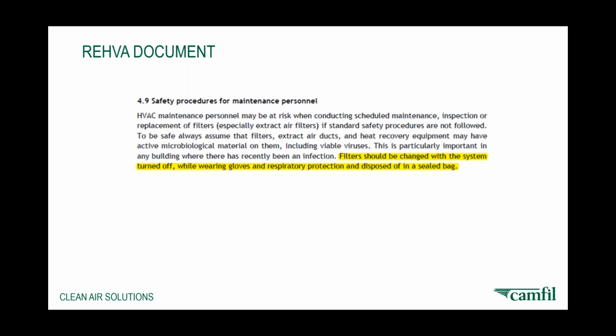And whilst we know that they will die and won't be viable after a number of days, you still have to treat them as potentially infected. If it was a pharmaceutical facility or a containment facility, you'd be using perhaps bag in, bag out, safe change, if anybody's familiar with that type of change of filters for either potent compounds or potentially hazardous filters. Here we're dealing with general ventilation systems, but we should still, in this current crisis, be aware of what's possibly inside the filter and always have our maintenance personnel protected with correct face coverings, masks as high a class as possible, and gloves, etc., etc.